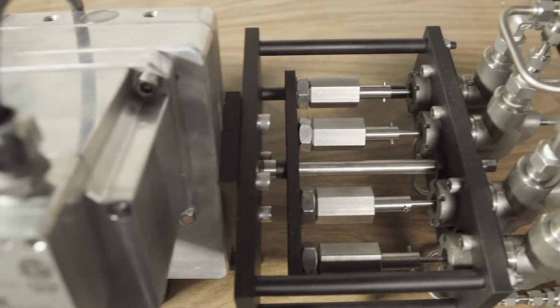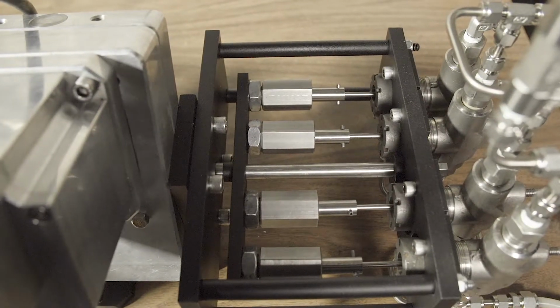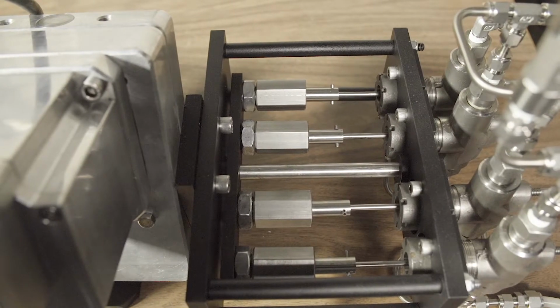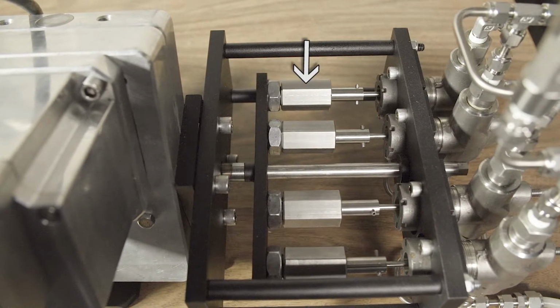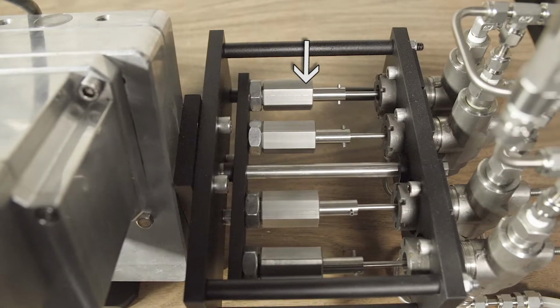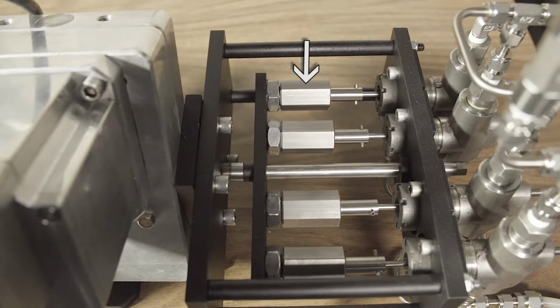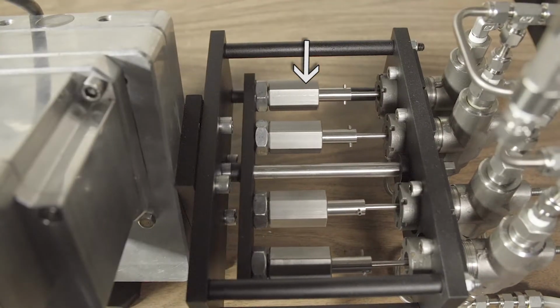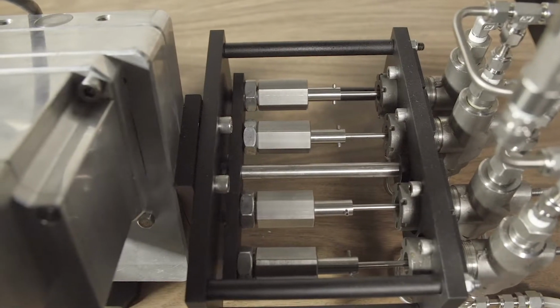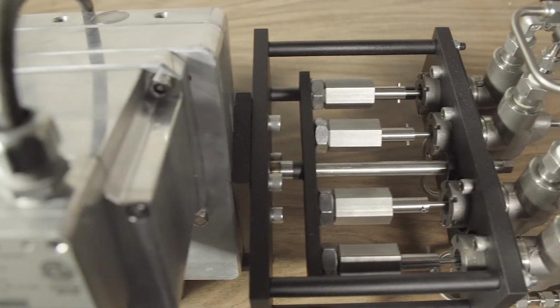The Trido chemical pump packages are powered by a single motor, so all the chemical pumps operate at the same speed. The volume delivered by each pump is adjusted by changing the stroke length of the pump using the adjustment nut. Trido has developed a spreadsheet that simplifies adjusting each chemical pump. This will ensure that each of the individual chemical pumps flow the required flow rates.